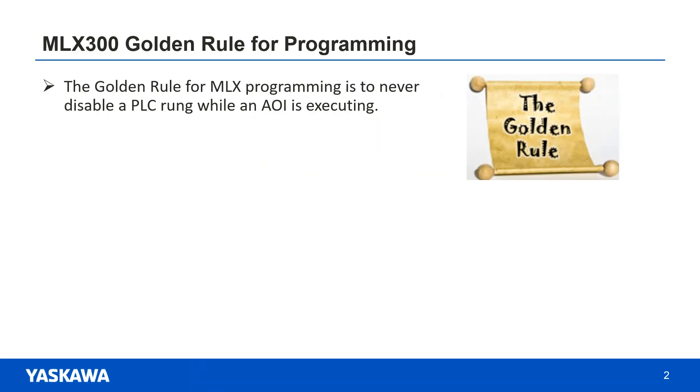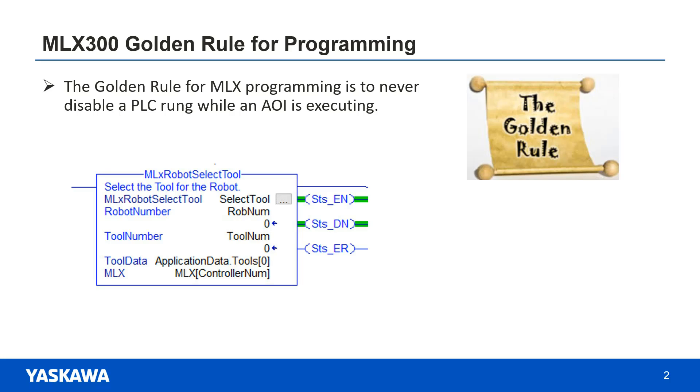The number one rule for MLX programming is to never disable a PLC rung while an MLX command is executing. Wait until the AOI has completed. This can be determined by monitoring the status done bit or the Sts_DN bit.